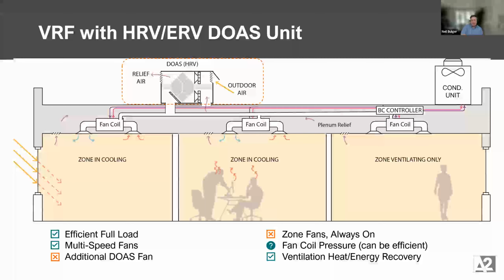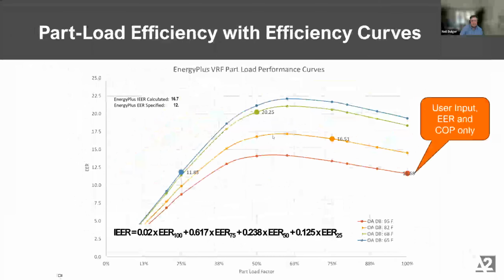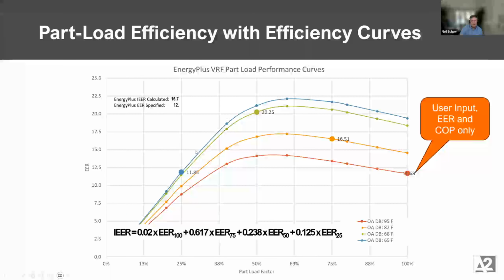Yeah, that's a really good point, because it's certainly a more forgiving system at part load, but it's not perfect, right? Even at low loads, it will still drive back towards inefficiencies, just like any compressor-based system. So it's probably more forgiving than other types of HVAC on oversizing and having that extra capacity. But it's always good to do a good calc and aim for 750 square foot a ton, right? Try and get the most out of these systems we can.